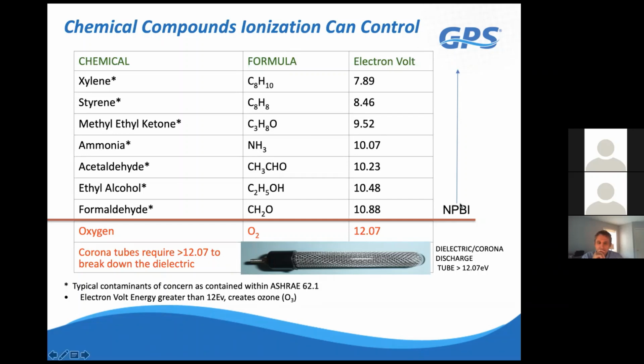Now with our technology, you see this red line, that's at 12 electron volts. So everything below 12, we can break down effectively. Everything above 12, we do not, because the energy is not high enough, which we specifically turn off there because we don't want to ionize oxygen in this application. When you do that, you get ozone, and that's an undesired byproduct, which all of these older systems are going to create with the glass tube, because for them to conduct electricity, they have to operate slightly above this threshold.